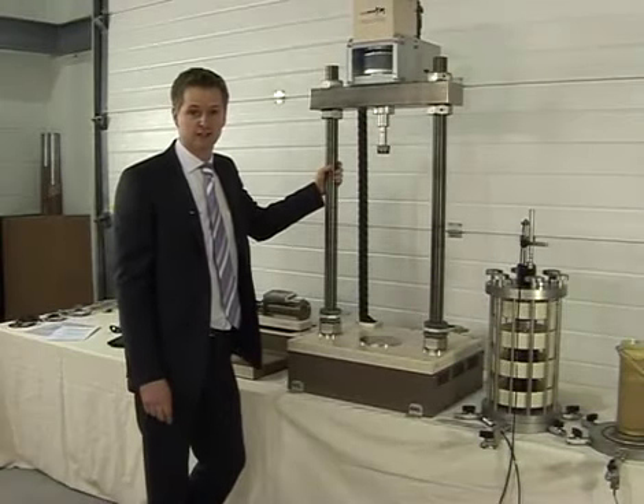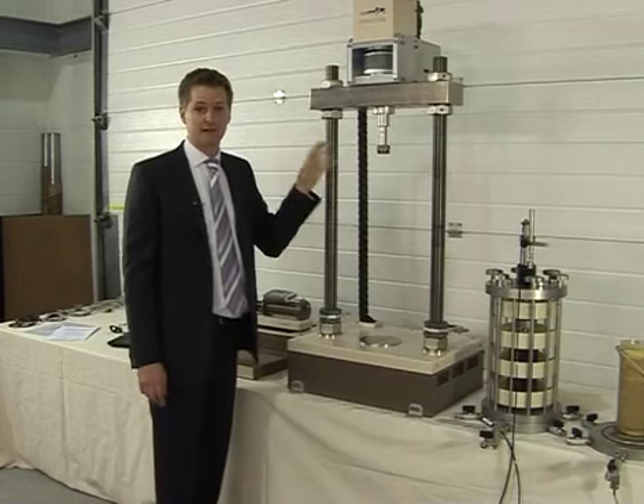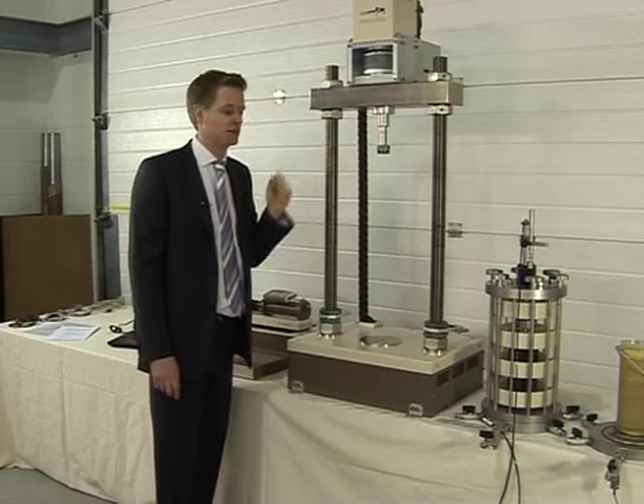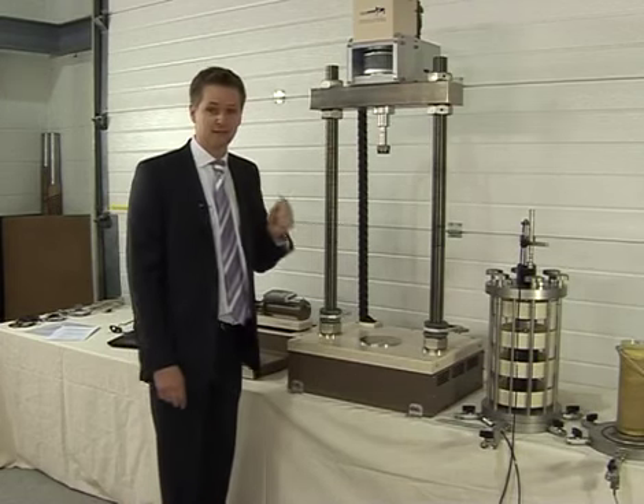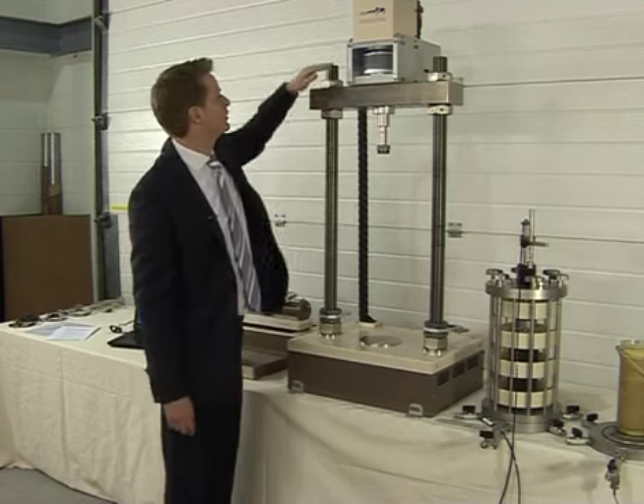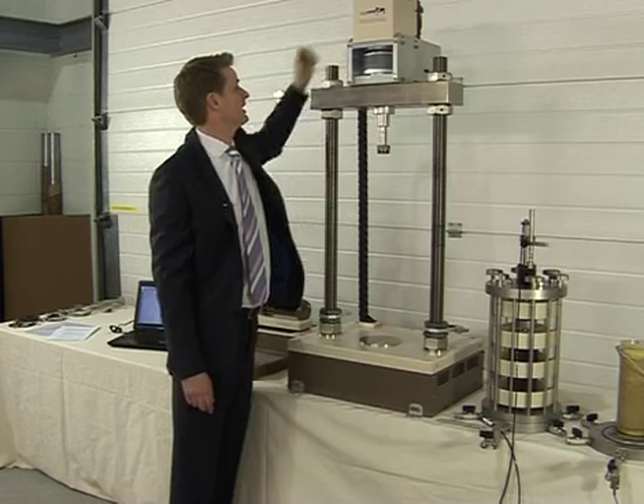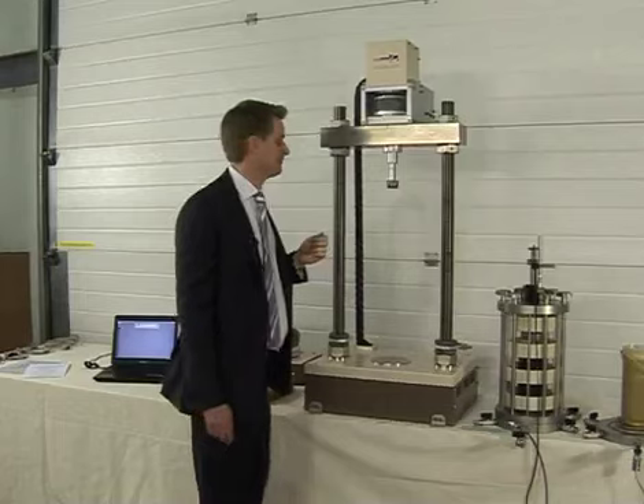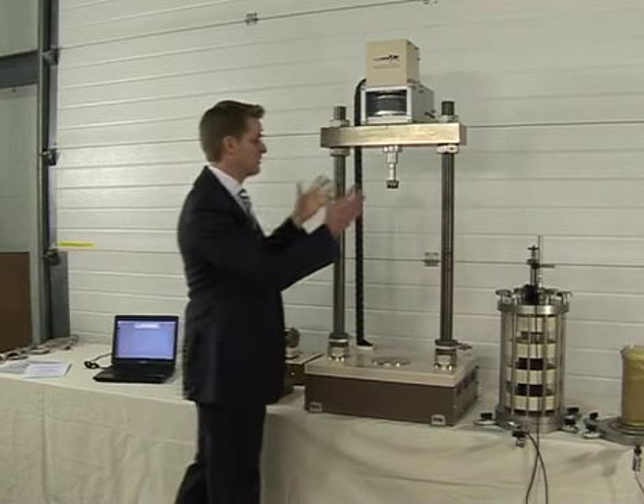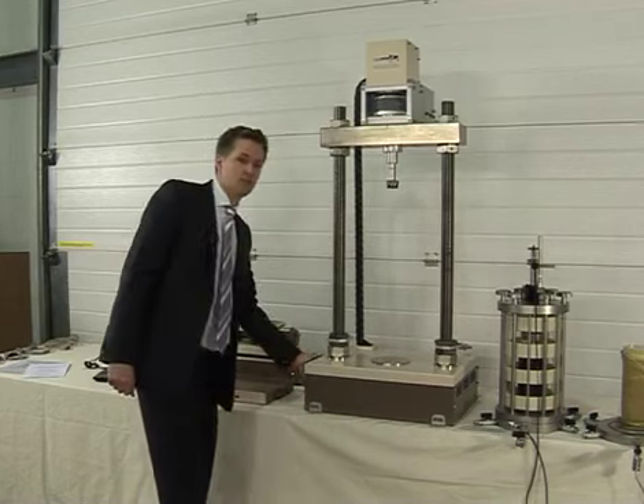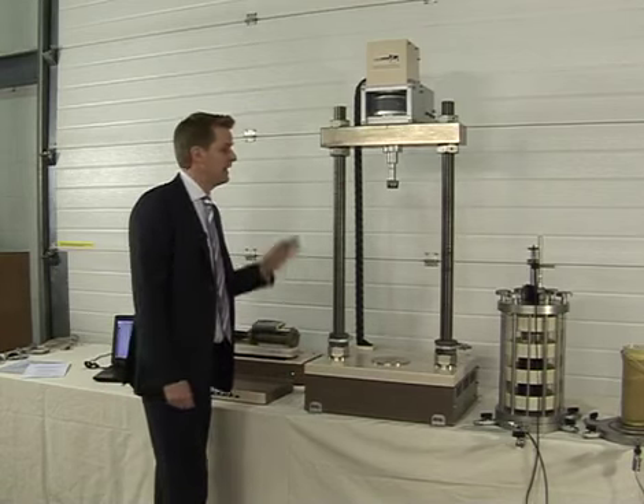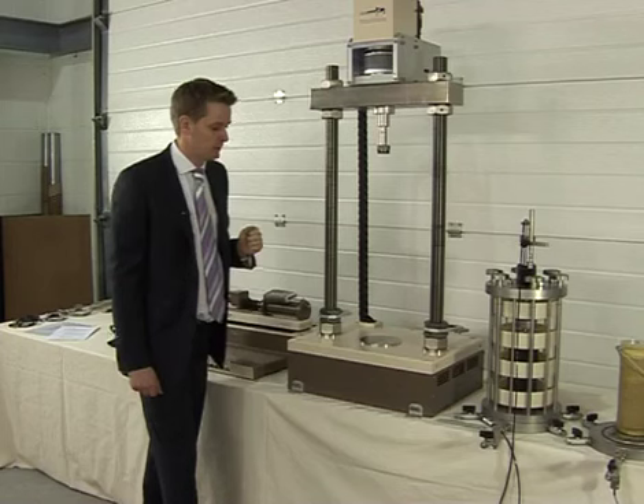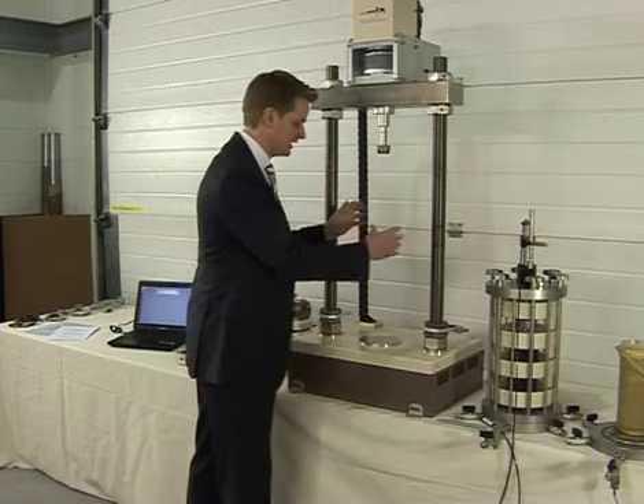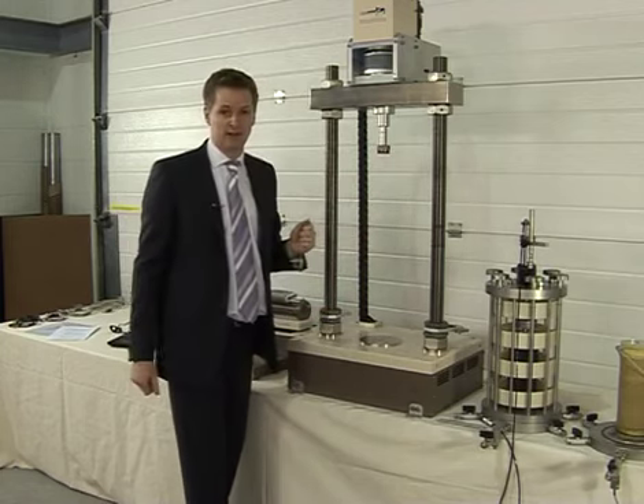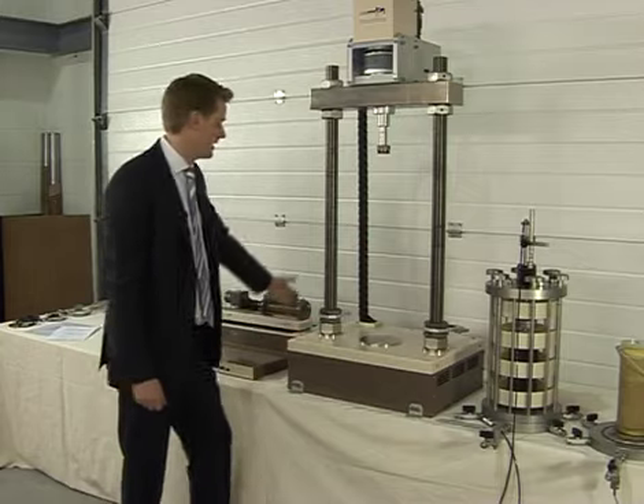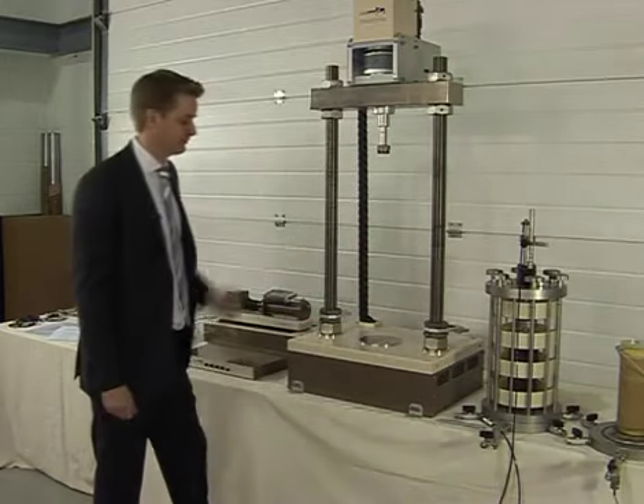Unlike a traditional triaxial setup, a dynamic actuator moves very fast, and it certainly has the capability of moving very fast. So one of the most important aspects is safety when working with this piece of equipment. Of course, it has limit switches which will stop it at any time before it reaches any physical end stop. But in terms of working around the equipment, we must always have the stop button pressed. The stop button will stop any action of the actuator at any time. In fact, we thoroughly recommend, when setting up the triaxial cell, setting up the sample, or moving anywhere around the actuator, that you both have the stop button pressed and you turn the device off at the back of the machine.